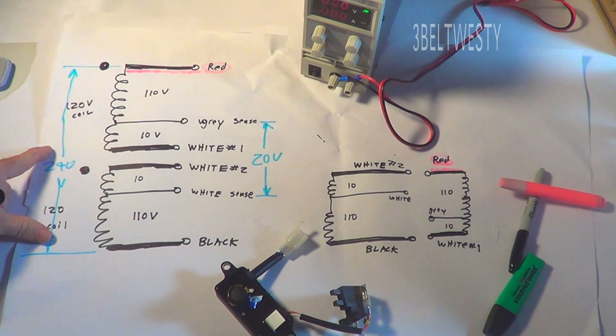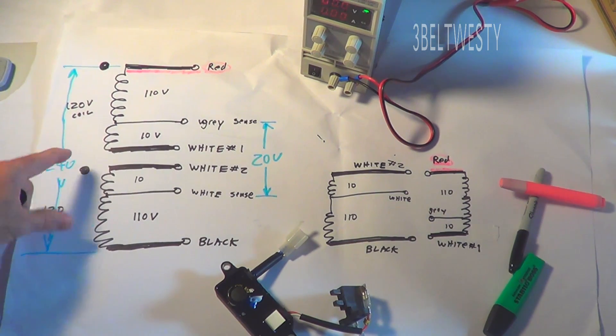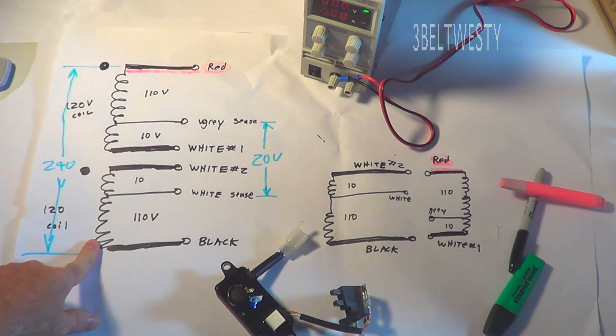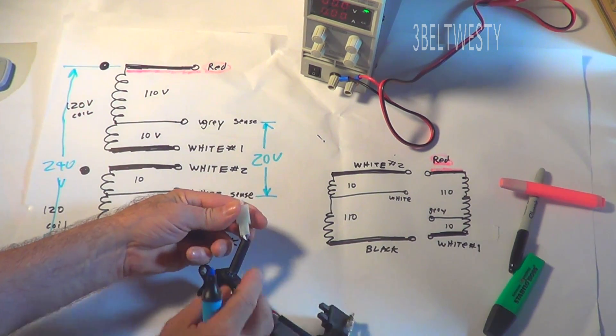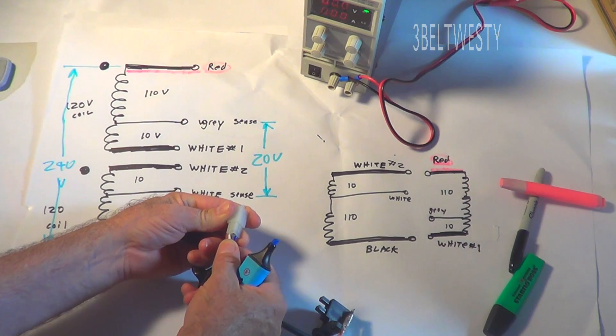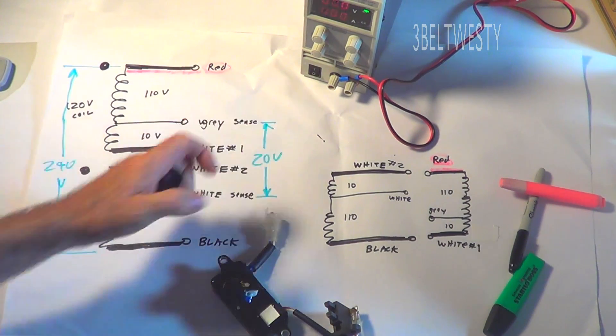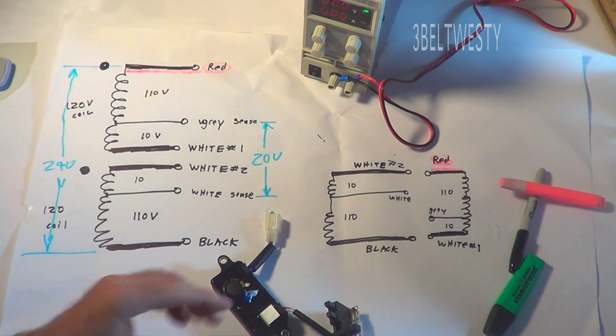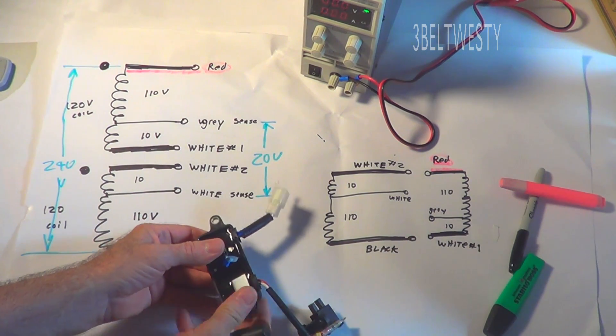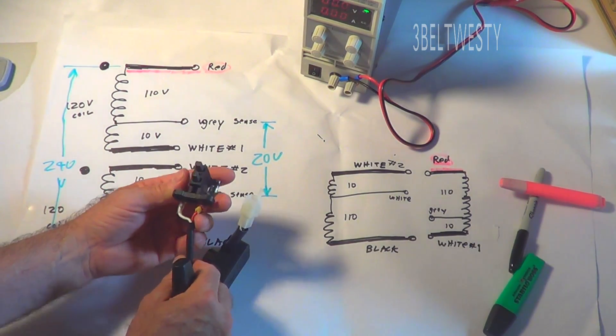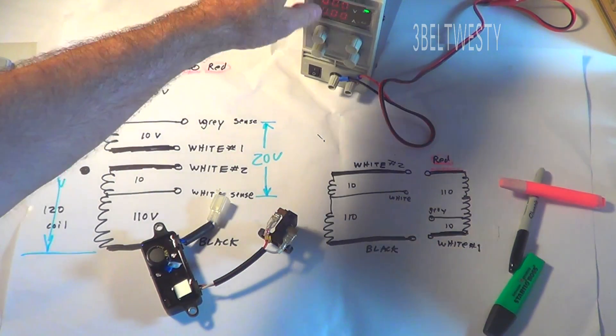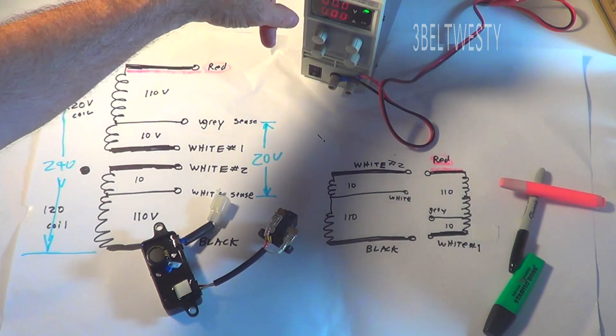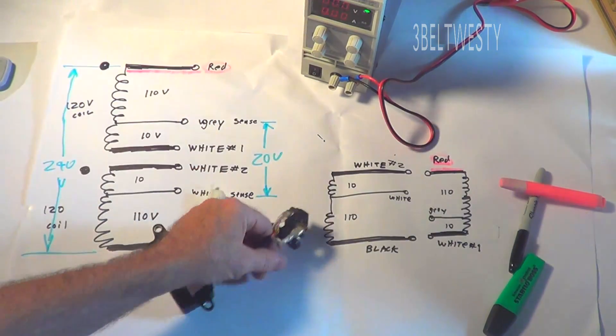Over here you have 240 volts. So in unmodified condition, you got 240 volts here across the entire set of both windings in series. And then what the AVR is sensing here, which is the white and the gray, is looking at the 20 volts. The AVR is what controls the voltage on the generator. It's got DC output to the brushes between 0 and 90 volts.